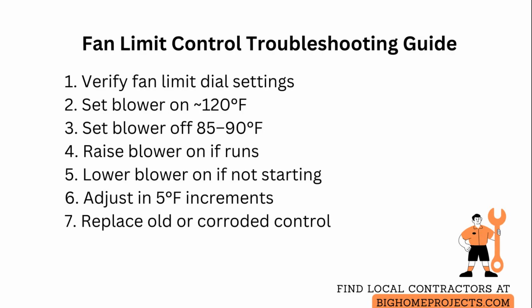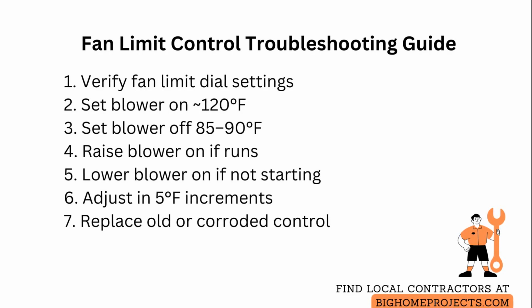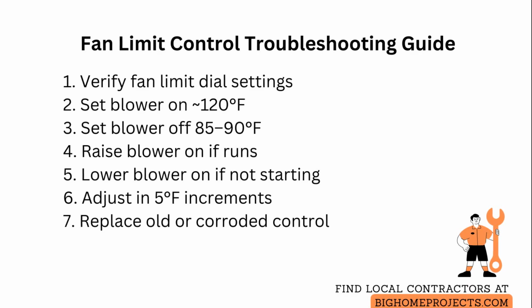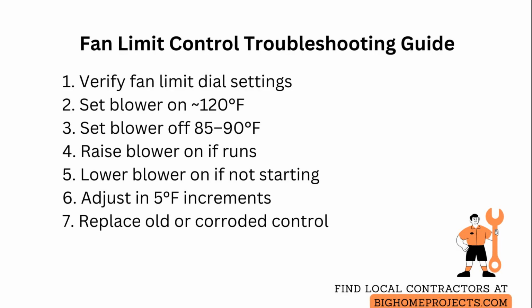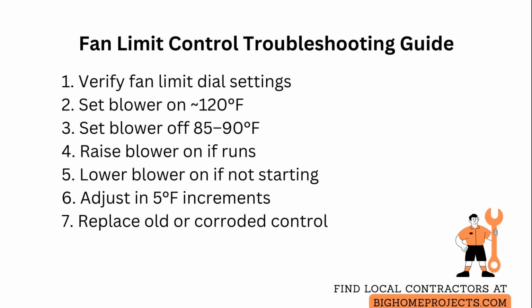First, verify the dials. The blower on temperature should be set around 120 degrees Fahrenheit, and the blower off temperature should be between 85 and 90 degrees Fahrenheit. If the blower runs continuously while the plenum is cool, raise the blower on set point slightly to avoid the control thinking the plenum is still warm.